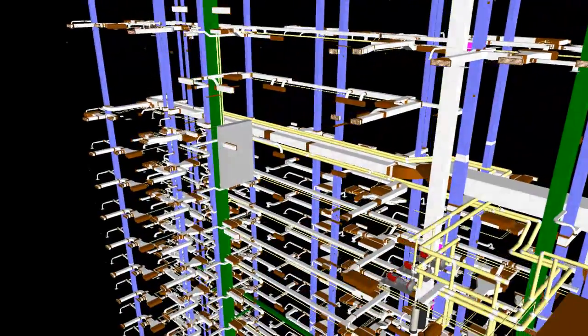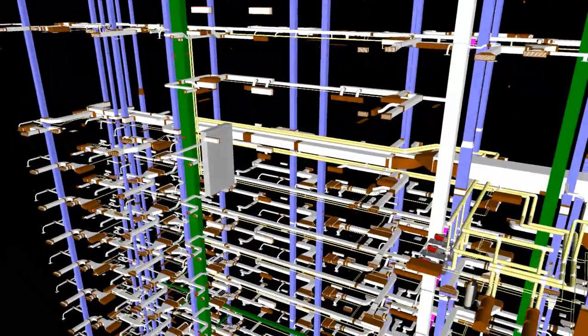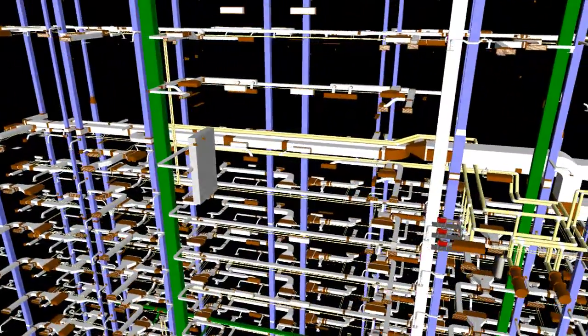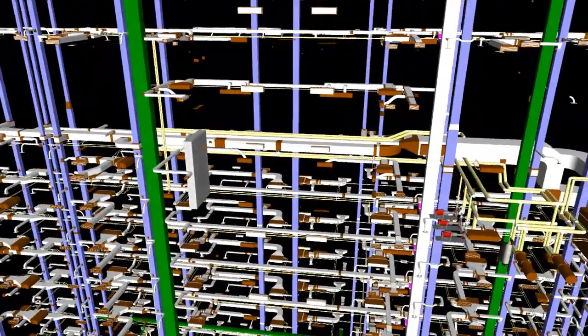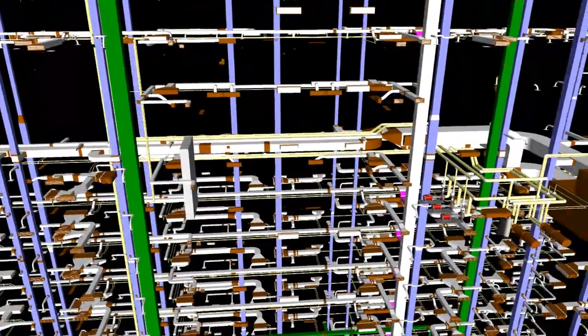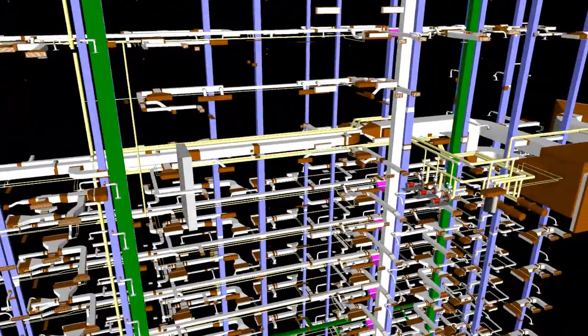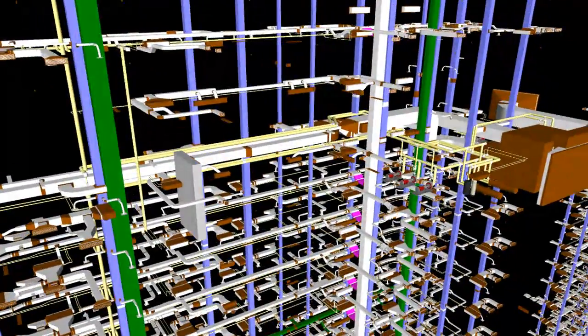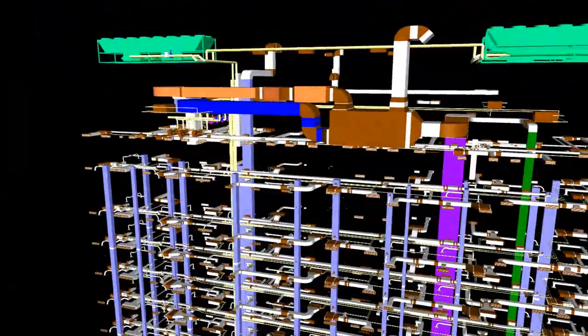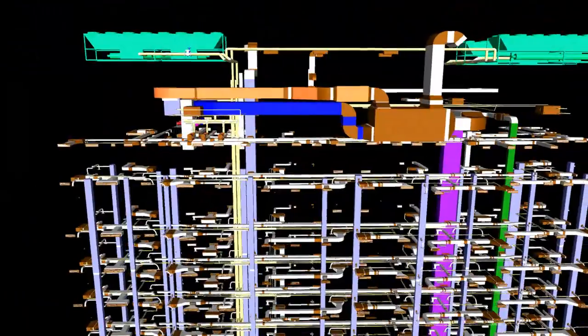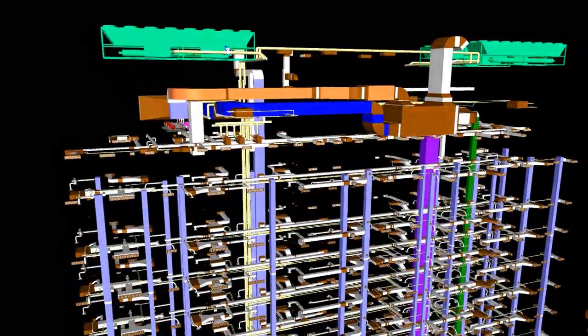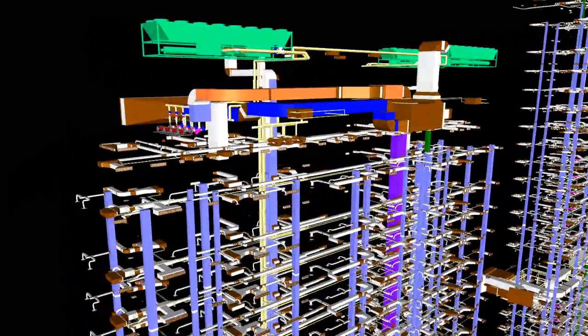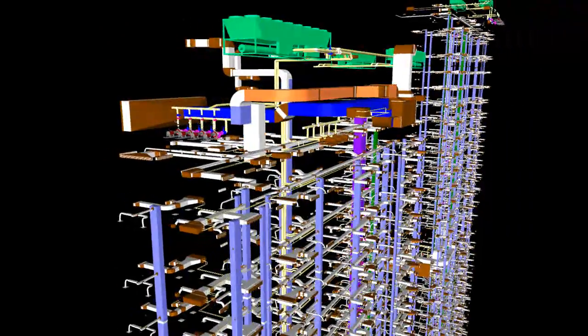Point 1: Air conditioning system. Air conditioning shall be provided by central chilled water system using packaged type air cool R-134A screw chiller units without standby provision having microprocessor-based control system. Single riser: One riser per building shall be used to serve the entire building chilled water requirements. The chilled water pipes shall run above the corridor ceiling void to serve all the spaces.